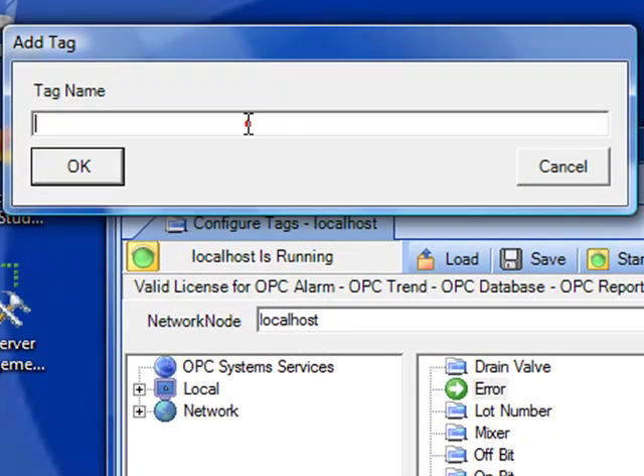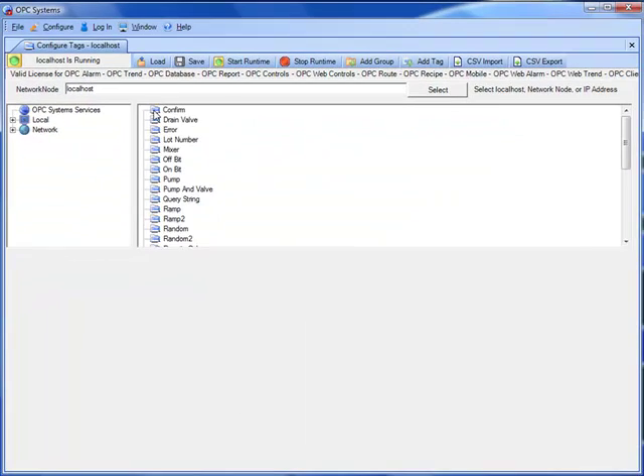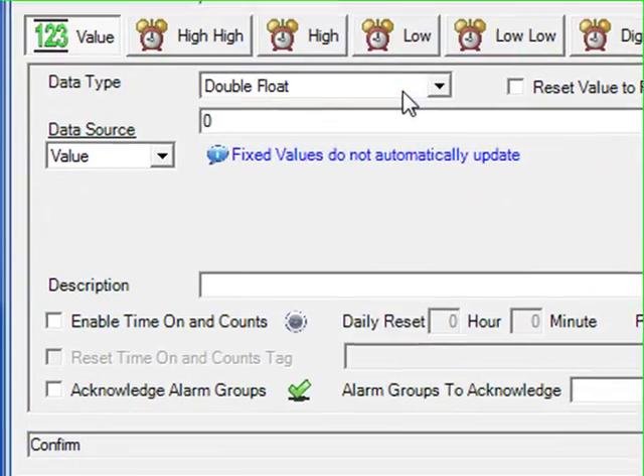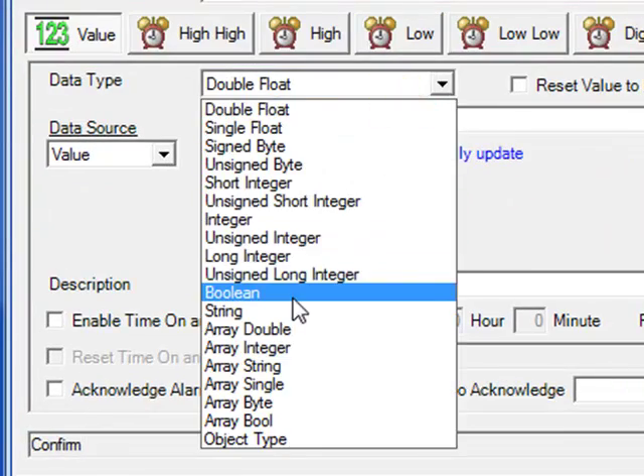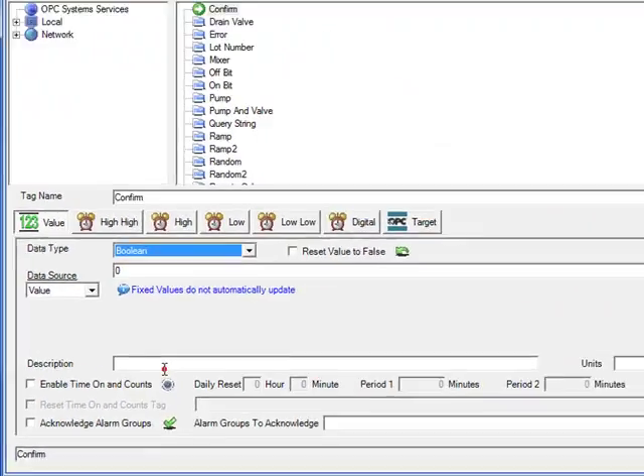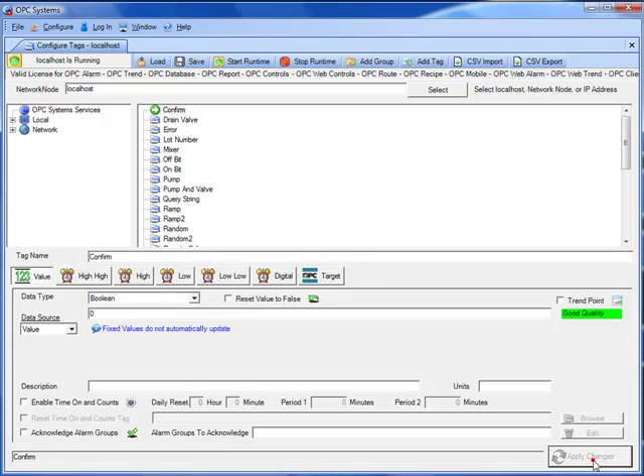And the final tag we will add will have the name Confirm. Select it from the tag list and set its data type to a Boolean. The confirmation tag will be set to true when the recipe execution completes successfully. If there's an error, that will be false and the error tag will have a non-zero number in it.